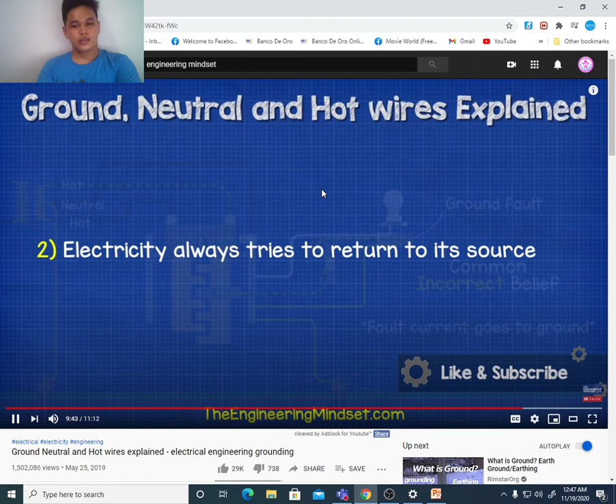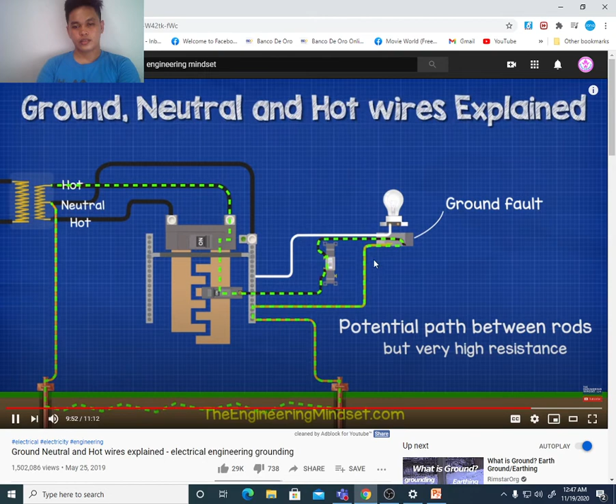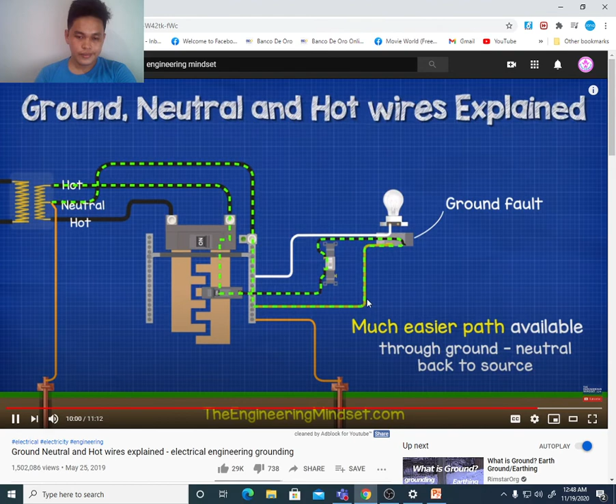Dito medyo mataas yung resistance sa ground compared dun sa neutral o saka dito sa ground pabalik ng source. Have a very high resistance or impedance. And as we know, electricity will take preference over the path with the least resistance. So balik sa source kung saan yung pinaka less resistance. Much easier path available through ground to neutral, back to source. So as we already have a very low resistance ground wire which provides a path directly back to the source, the ground, so lightning is...